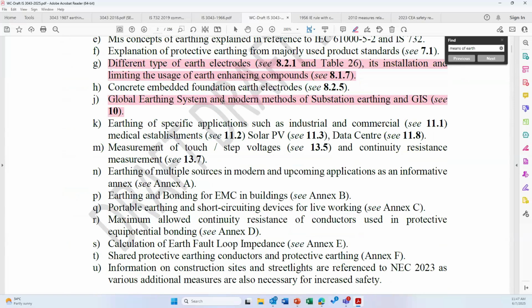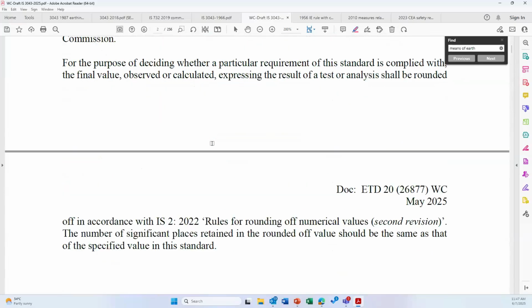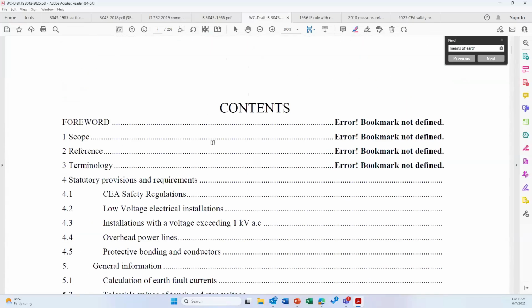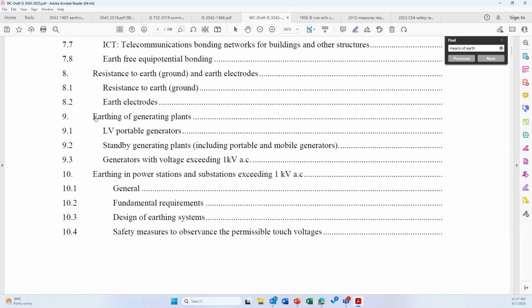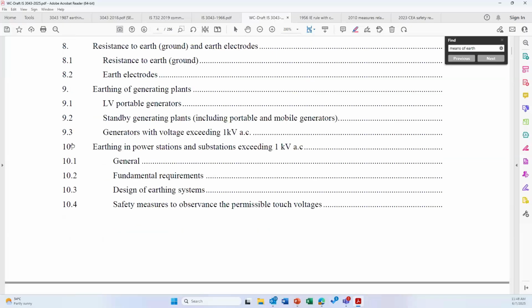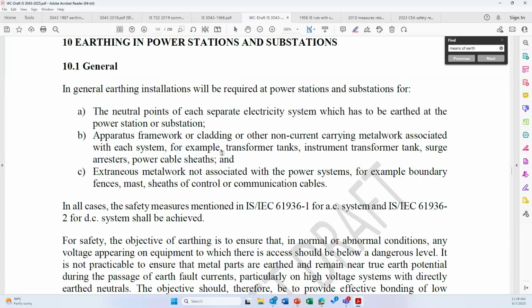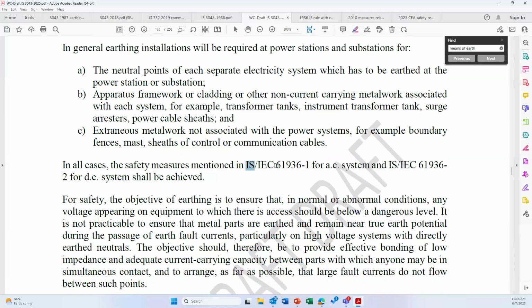This time, a lot of modification has been made in this particular subject, the subject of earthing in substation. This is coming in chapter 10. Chapter 9 is talking about the earthing of generating plant, means generators, DGs, high voltage, low voltage DGs. Chapter 10 talks about earthing in power station and substations. So here the information are from IEC 61936.